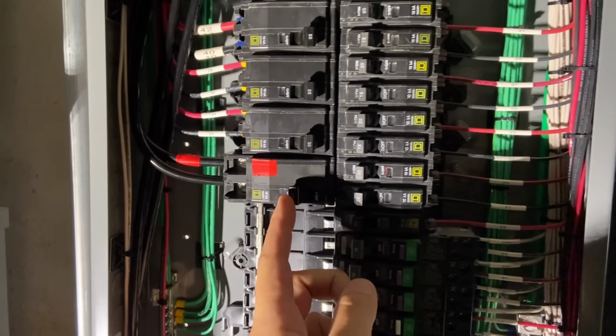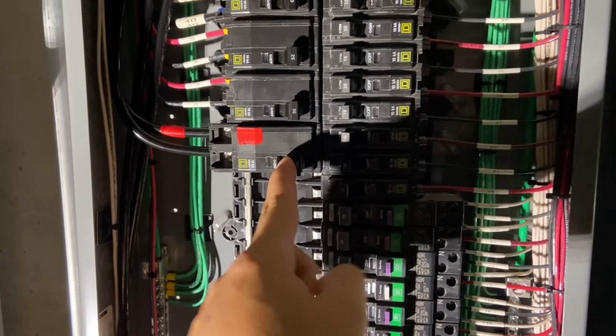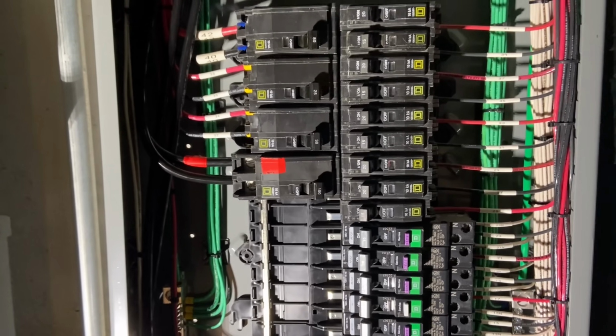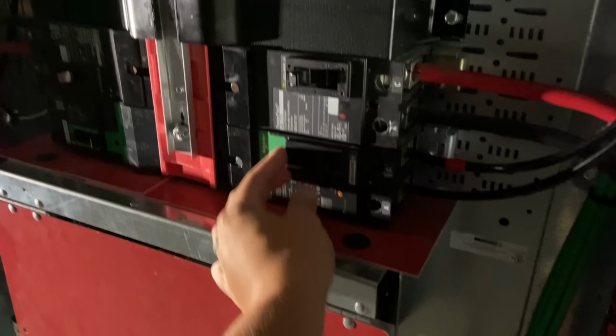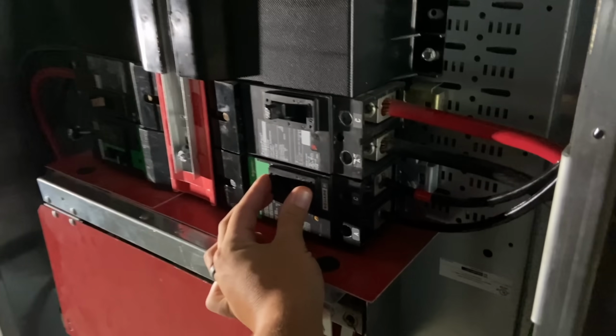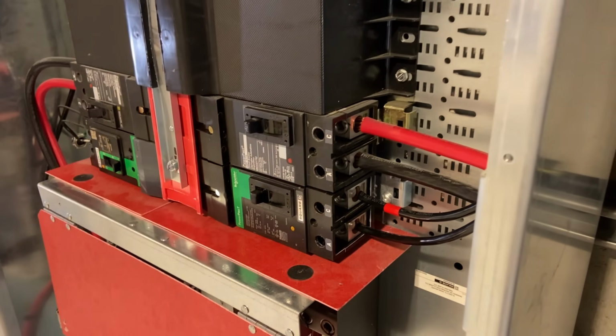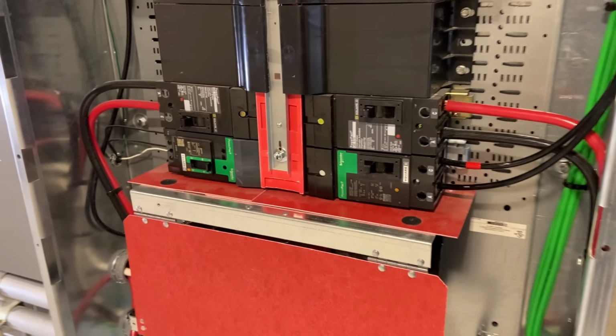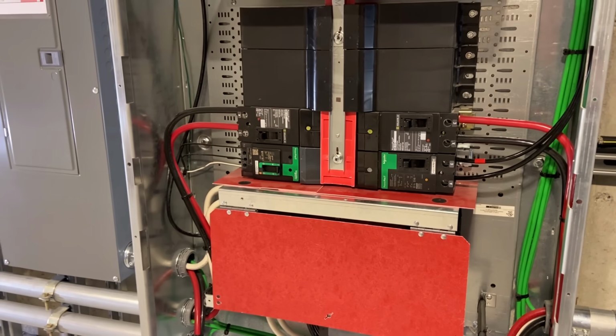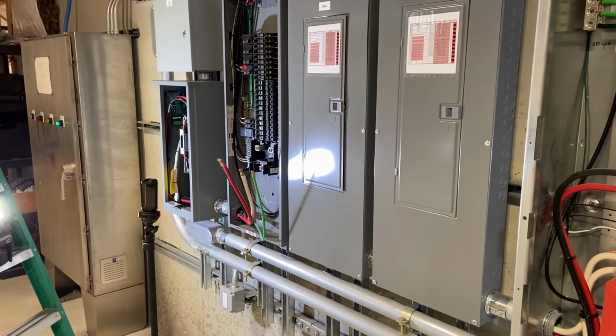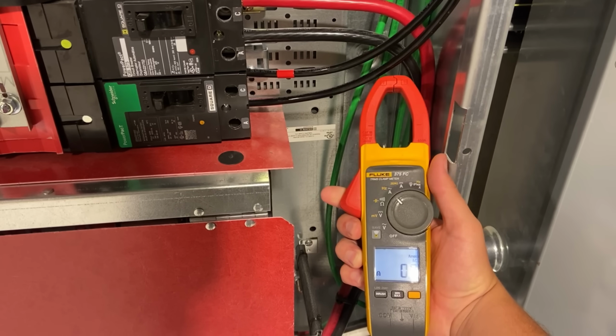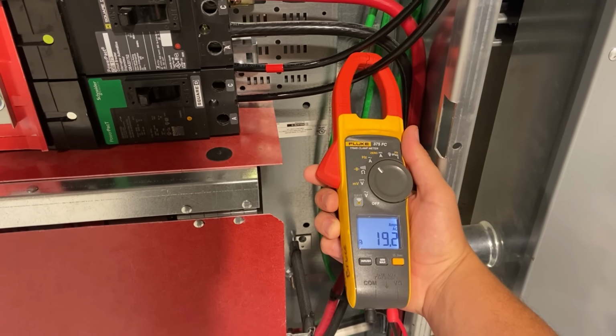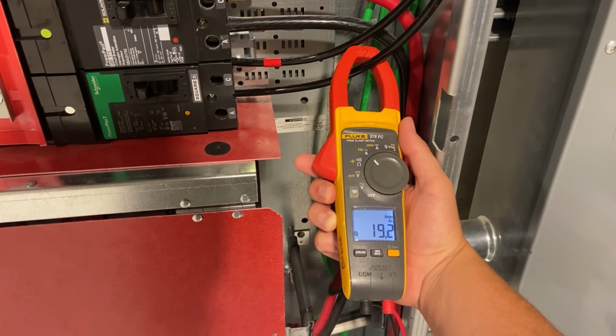But now that our wires are unhooked from the panel, we can turn that breaker on, which nothing happens because the one in our large panel is still off. Turn that on, and look, we have light again. And if we did it right, we don't have anything backfeeding to hurt us. So now we just got to tear everything apart properly. If you're curious about how much current we're drawing at this moment, about 20 amps.